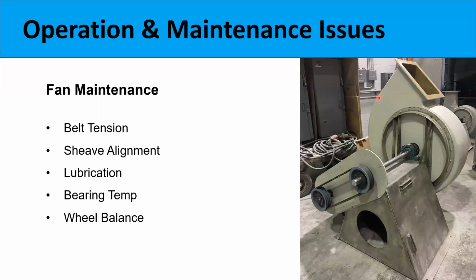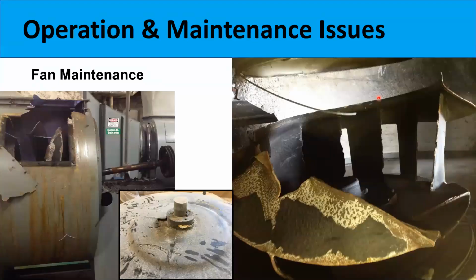Maybe you're operating the system and there's some bypass getting through the scrubber, or you're salting out in the scrubber and you're getting salt formation buildup on that wheel, causing it to come out of balance. And it's a maintenance activity. Go in and you can clean that wheel up, and oftentimes it will take care of that out of balance situation. If you don't keep these things in balance, then you can have catastrophic failures.